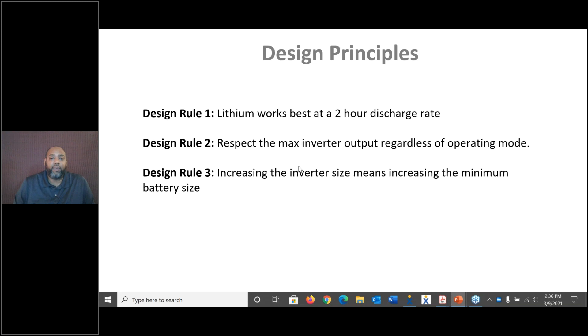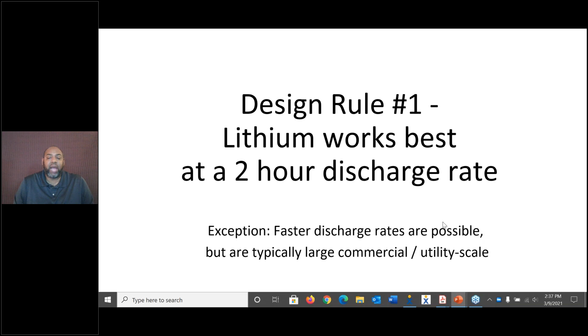So lithium works best when it's discharged at a 2-hour rate. And the reason is that the voltage is more stable when compared to a flooded lead acid battery. It allows for more stability of the battery in the voltage range, and you won't have that battery dropping out. So when you go to a 2-hour battery chart, this is a 48-volt battery chart here, and you're looking at the discharge rates over here. If you notice, the voltage stays pretty stable from 10%, really low, all the way till you get to 80%. The voltage stays pretty flat.